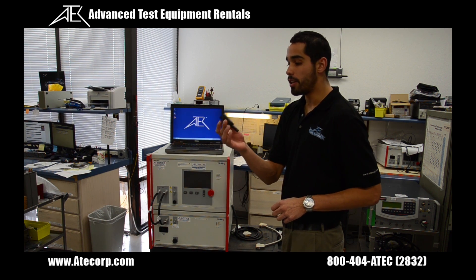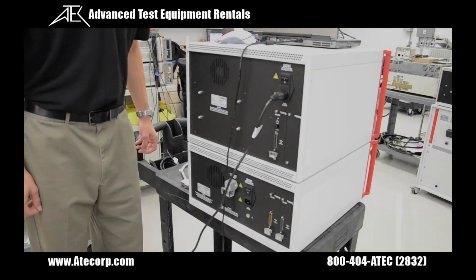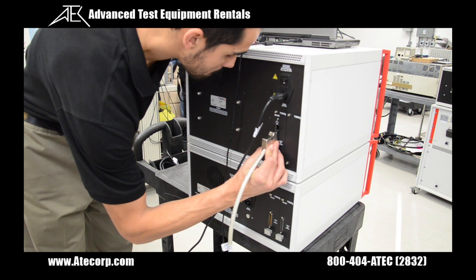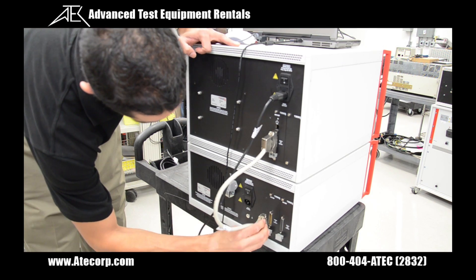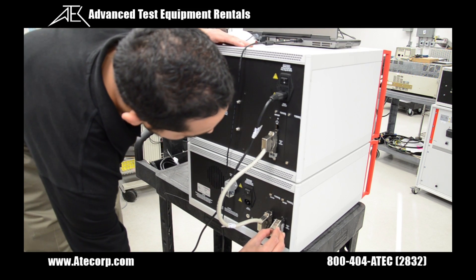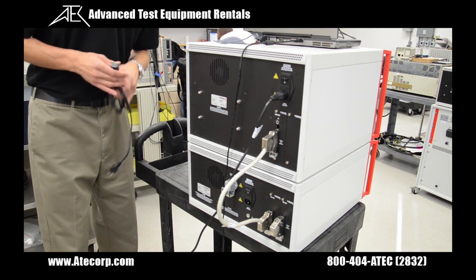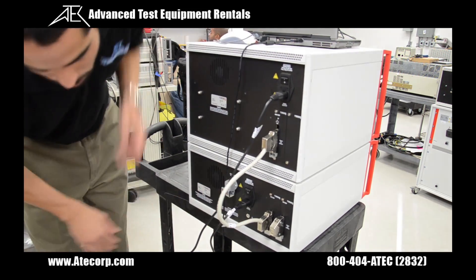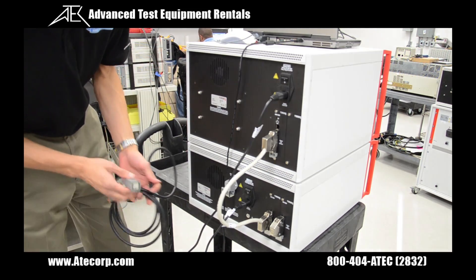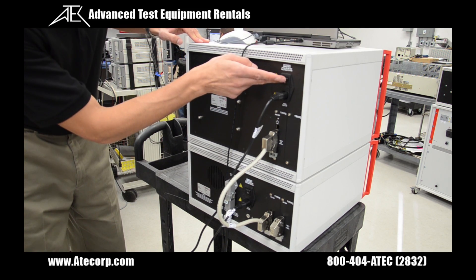Now I'm going to insert the EUT connector, which you're going to have wired into your EUT. On the back of the instrument, I'm going to connect the intercommunication cable, then the interlock connector, the CDN's power cord, and finally the EUT's input power cord. Then I'm going to flip both power switches on.